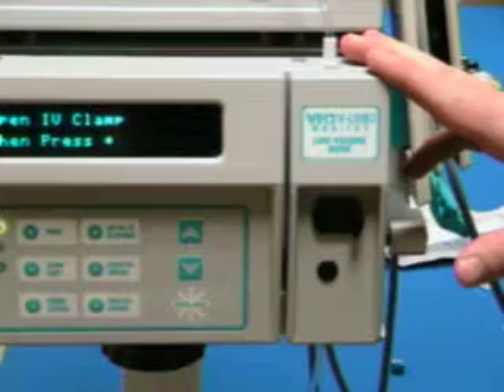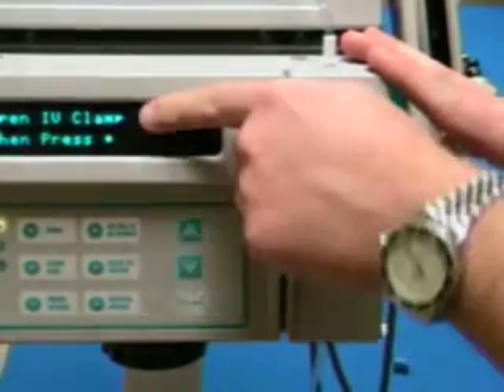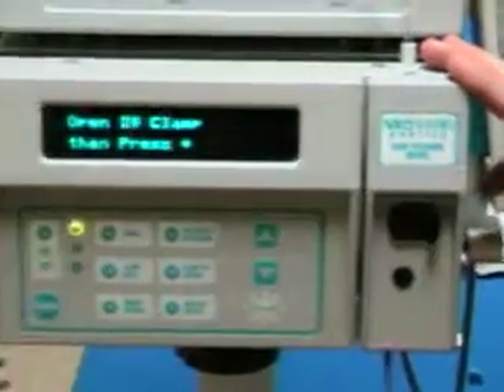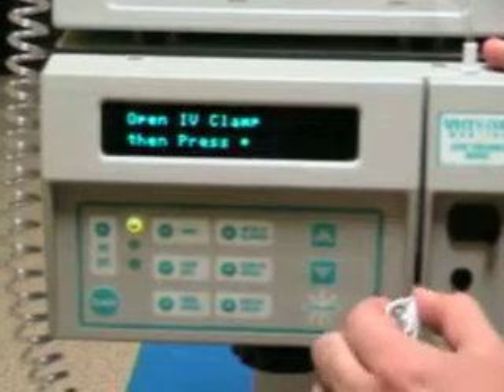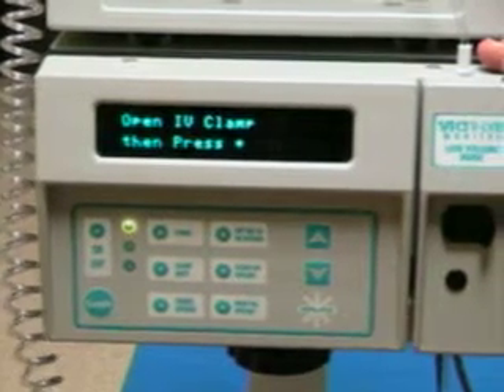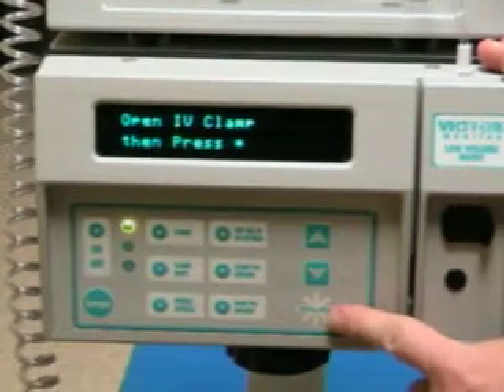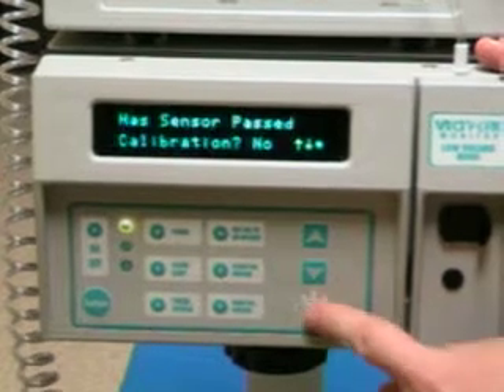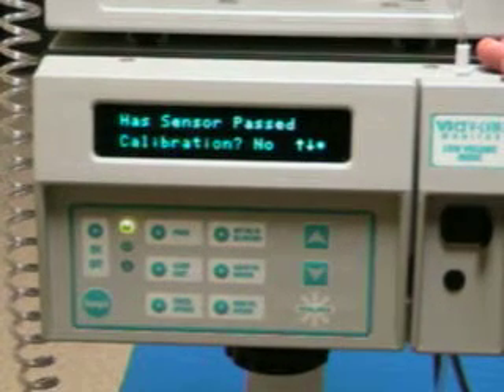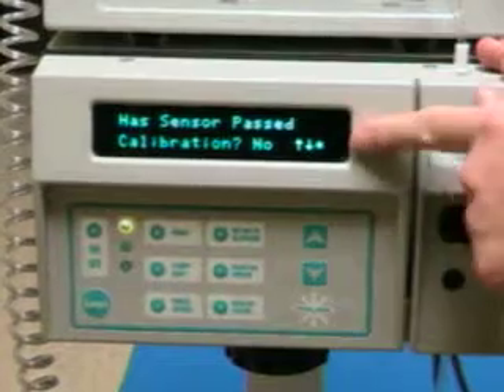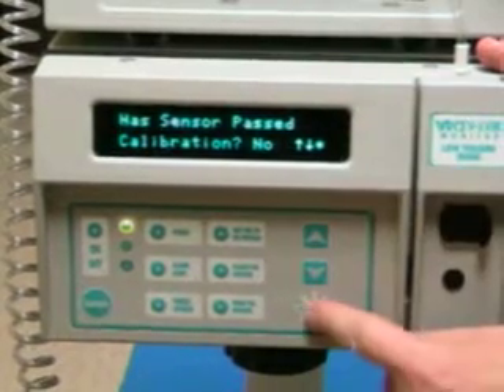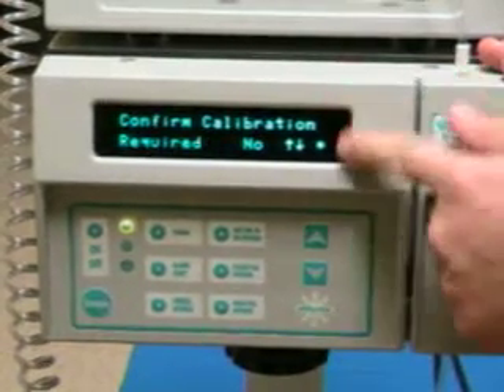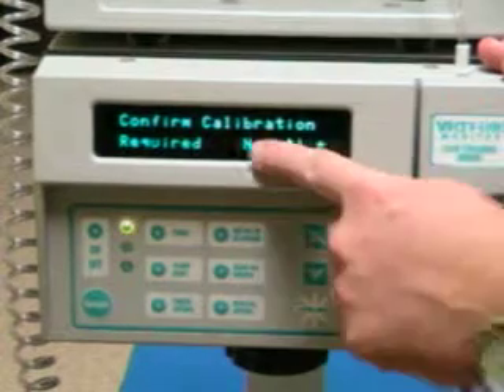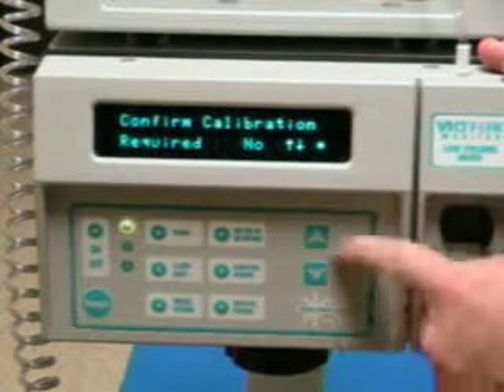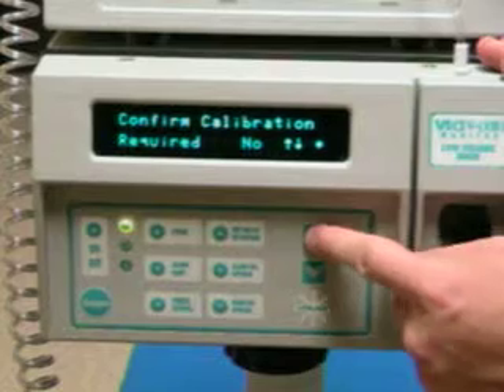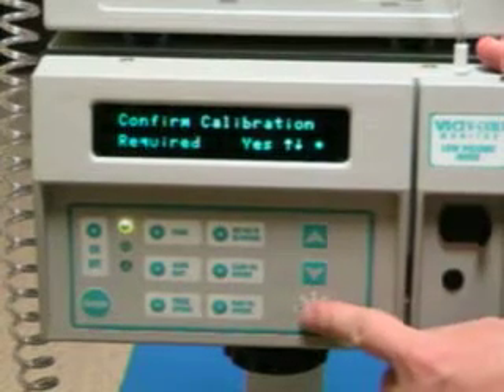Now this is immediately going to sense all that, and it says open IV clamp and press star. So we're going to open our white clamp down here and then press our star key. This is always our acknowledgement key. Has sensor passed calibration? No, it has not, so we'll acknowledge it with the star key. Confirm that calibration is required. It says no, but we want to change our answer to yes, so we've got the arrow keys to do that. Switch it up to yes and hit asterisk.